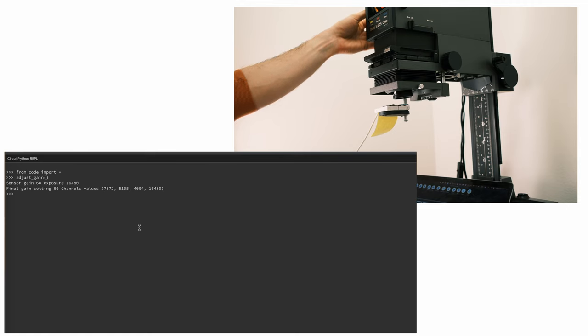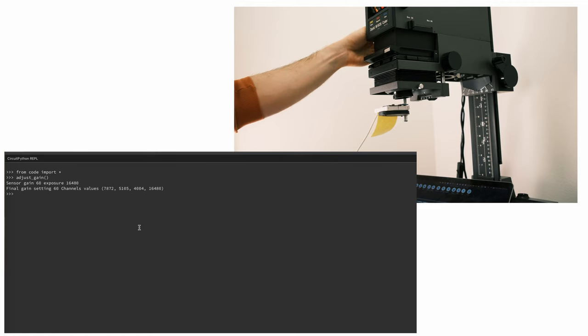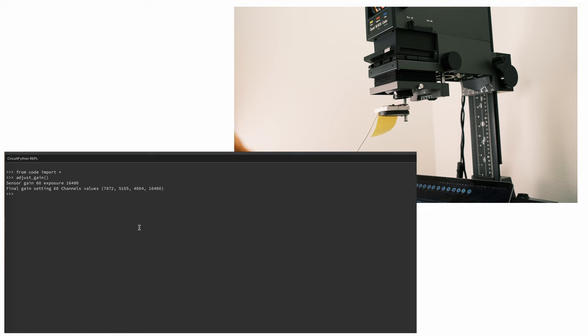For now the procedure looks like this: I adjust the gain, I close the filters, calibrate the minimum value with all filters closed, and from that I know the dynamic range of the full setup.